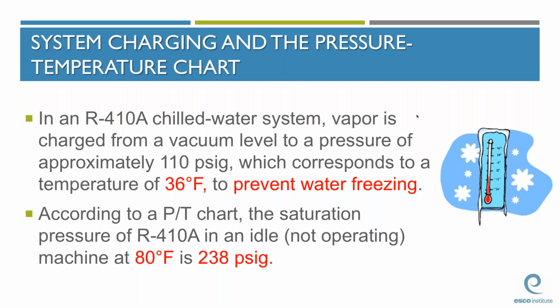So for example, if an R410A chiller is in a deep vacuum and we need to charge it, vapor refrigerant should be added to that system until the system pressure is approximately 110 psig. This pressure corresponds to a temperature of 36 degrees and will prevent the water in the chiller from freezing. Of course, in order to determine the pressure to which a system should be vapor charged, your students will need to know how to read a pressure temperature chart, so be sure to give them lots of practice with that.